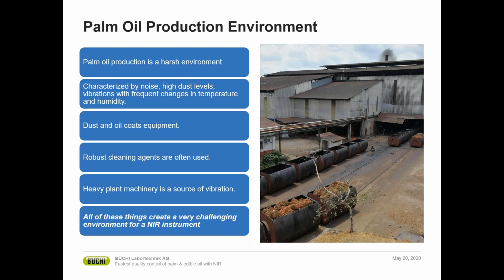As time goes by, a lot of dust and oil can coat the equipment that's in the palm oil production area. And to get rid of that, to clean the area, quite often the operators use robust cleaning agents to clean that dirt and oil off the equipment. In addition, there's heavy plant machinery present, and that's a really strong source of vibration for the equipment. And so when we take all of these things together, it creates quite a challenging environment for an NIR instrument to operate in. And if we think of older pieces of equipment that are out there for measuring NIR, they needed a nice, quiet, clean environment to be able to offer good, accurate NIRs. And so you can see that it's quite a challenging environment for the equipment to work in.